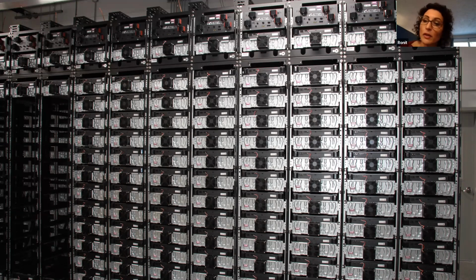What's in place is a regular sprinkler system and a dry agent Novec system. Each module is encased — our safety engineer likes to call it a scallop wrapped in bacon — because each battery is encased in that Novec safety component. So if one battery heats up and, in extreme situations, catches fire, it won't propagate to the next cell because of that bacon-like Novec encasement.